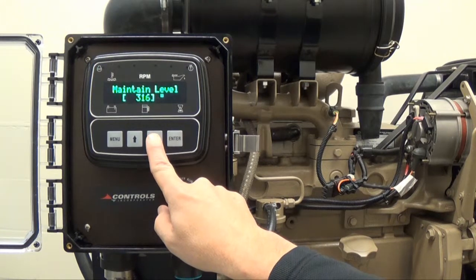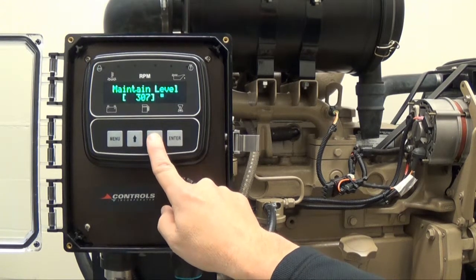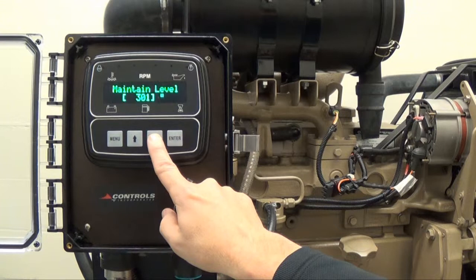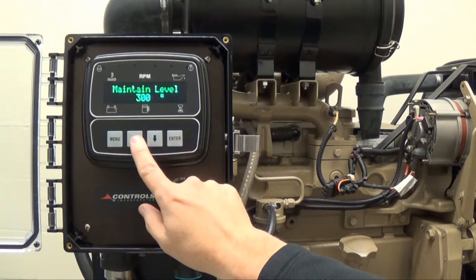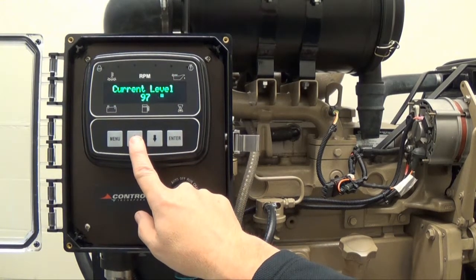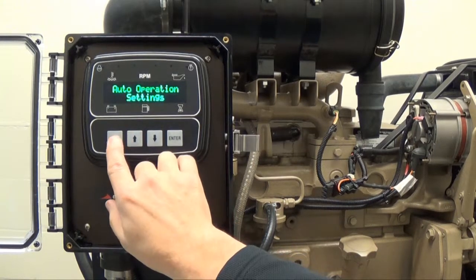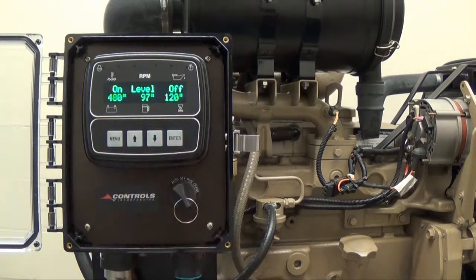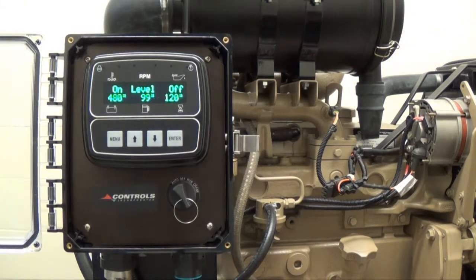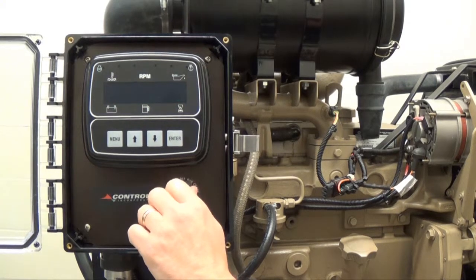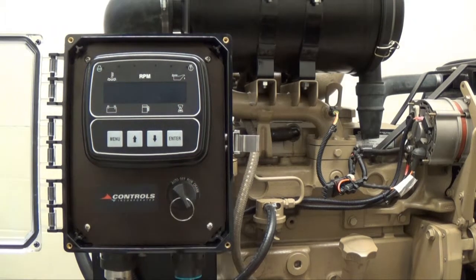Once you have reached the desired level, which in this case is 300 inches, then press enter to remove the brackets. Press the up arrow button to view the current level, which is 97 inches. Finally, press and hold both the menu and enter button at the same time in order to return to the normal engine operating display. Always cycle the key switch off and back on again to retain any menu changes.